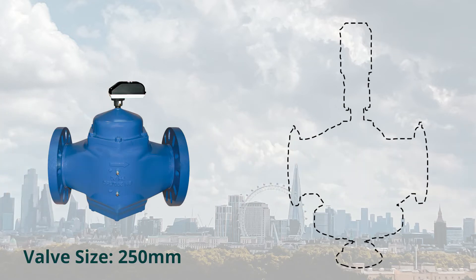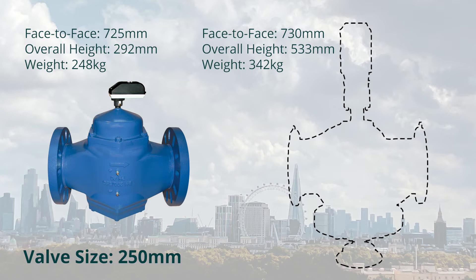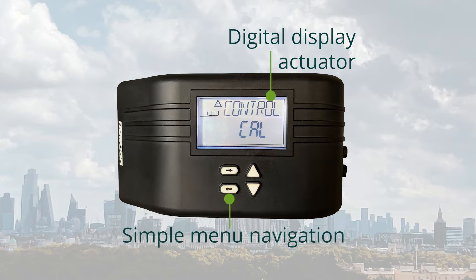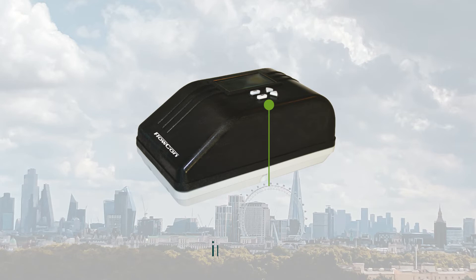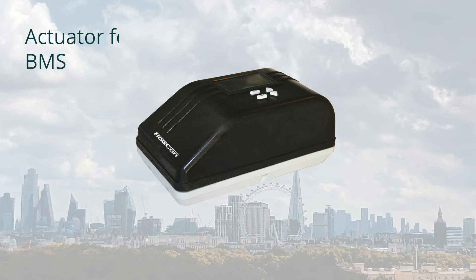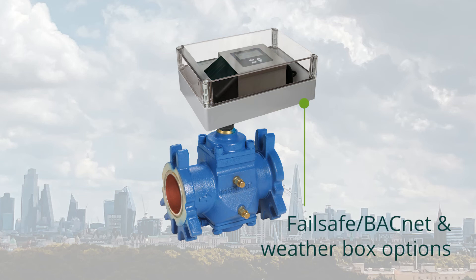The Flowcon SM is smaller and lighter than other valves on the market. The digital display actuator fits the whole range of valves. It can be password protected and locked. There is easy setting of flow, control mode input — equal percentage and linear. There is actuator feedback to BMS, and failsafe and BACnet and weatherbox options making it suitable for outdoors.